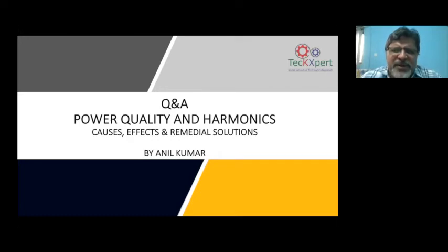If you have multiple VFDs running in parallel, then also harmonics come down, because every VFD has a particular firing angle at which it switches on and switches off. So all the VFDs will not work at the same firing angle. When the firing angle varies from VFD to VFD, the impact of harmonics also comes down.